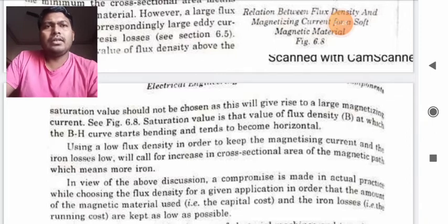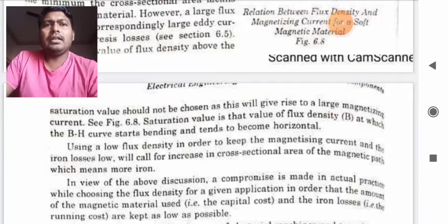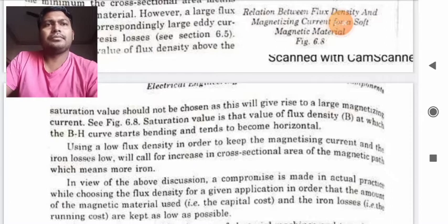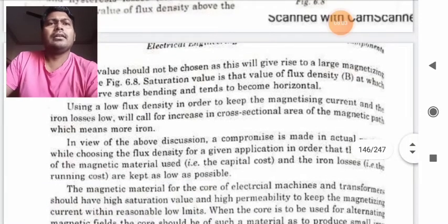Using a low flux density in order to keep the magnetizing current and the iron loss low will call for increase in cross sectional area of the magnetic path which means more iron. In view of the above discussion, a compromise is made in actual practice while choosing flux density for a given application in order that the amount of magnetic material used and the iron losses are kept as low as possible. So this is the compromise made while choosing a material.